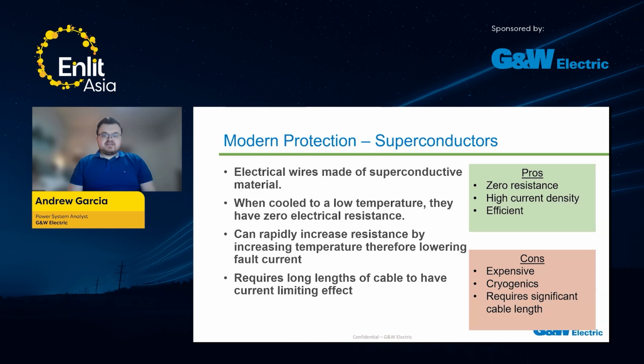Now, once again, there are a variety of cons to this, just to make sure it doesn't sound too good to be true for the audience. They're very expensive. Once again, superconducting material is not cheap, and it's likely to never be entirely inexpensive either. You're introducing cryogenics to your system, which is not only new, but it can also introduce a new hazard that your workers will need to be aware of. And just to reiterate, to massively increase the impedance and therefore limit current, you're going to require a significant cable length. You can see a lot of superconductors in HVDC transmission system designs, when you're moving a large amount of energy over a long distance, say from a massive solar plant or wind farm to where there's people.